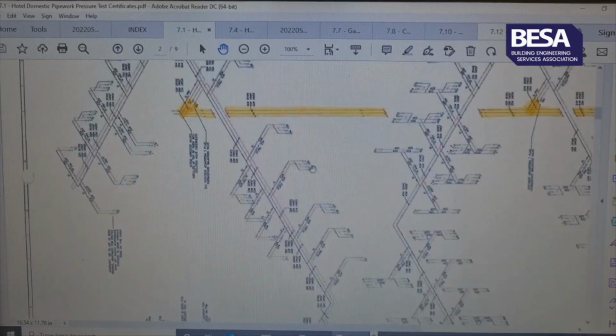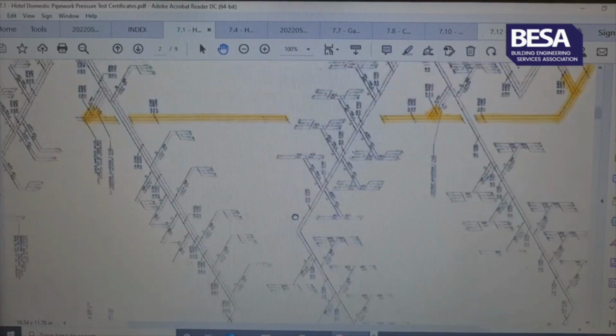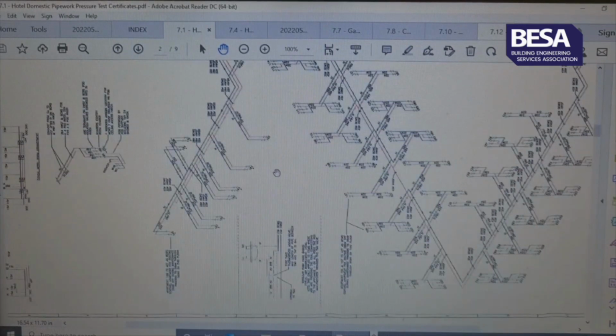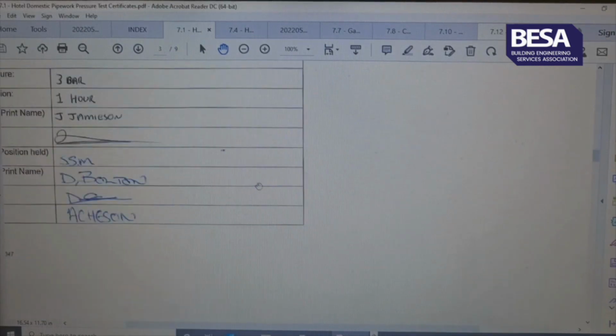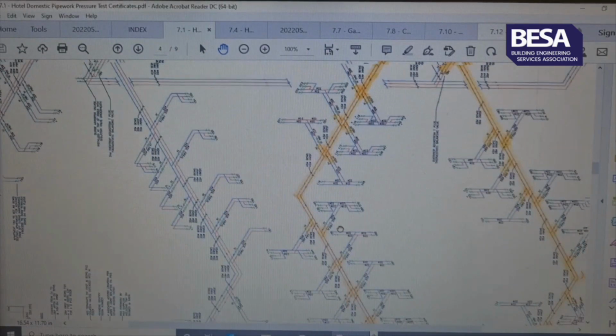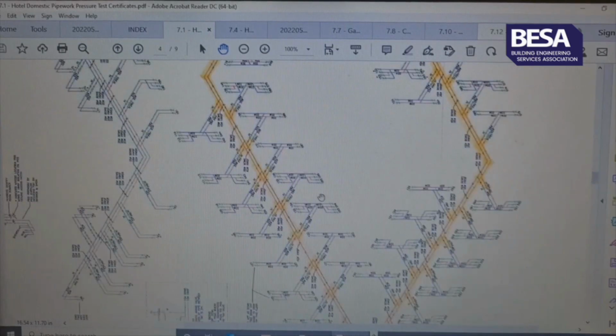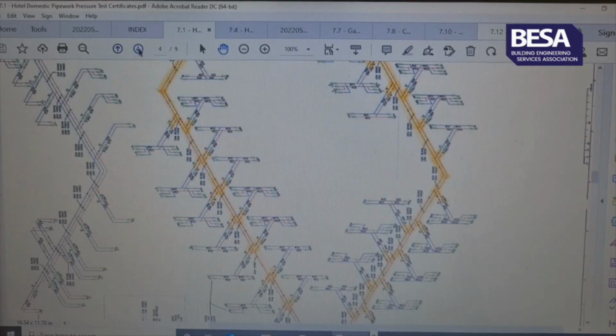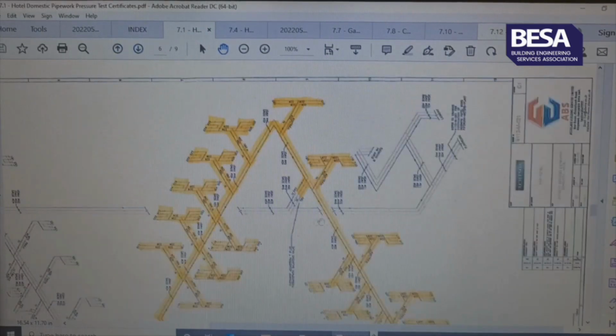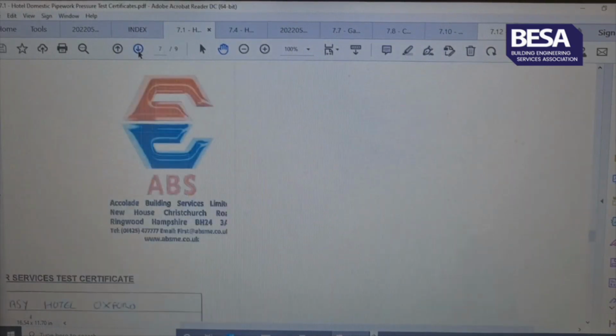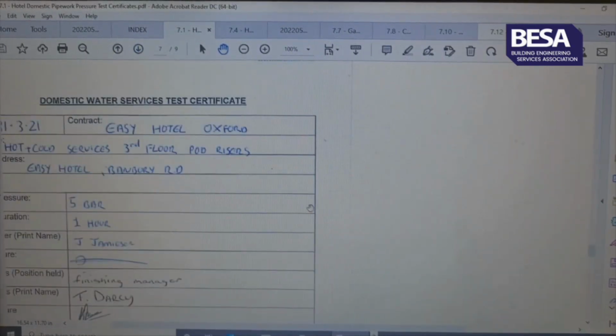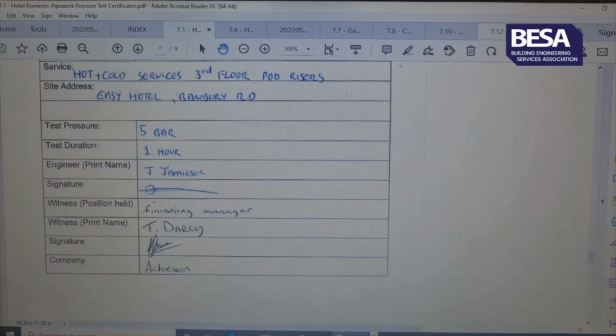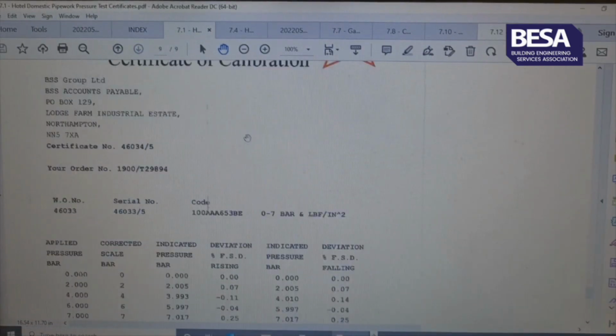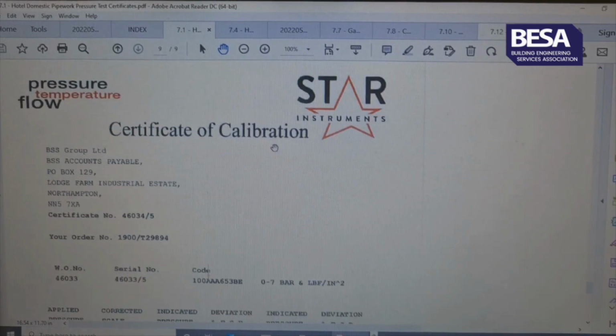So every bit of pipe throughout the building. It's actually an A3 drawing there, hence why it's the wrong way round, but there's a test certificate. We did a lot of sectional testing on this project, and then one big overall test on each floor for the domestic hot water and the domestic cold water. Again, that was all witnessed by the client, as you can see down there. And at the end there's a calibration certificate for the gauge that was used as well.